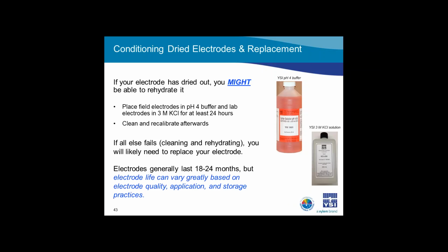As mentioned, you can try to recondition your probe, your electrode, if cleaning does not bring it back into spec or improve the response. Field electrodes can be soaked in buffer 4 overnight or over the weekend to try and rejuvenate them. Lab electrodes can be soaked in 3 molar KCl. If good calibration, slope, or response is not restored after cleaning and reconditioning, it's probably time to replace your sensor.